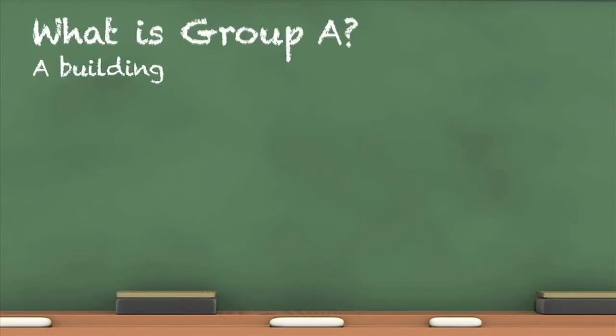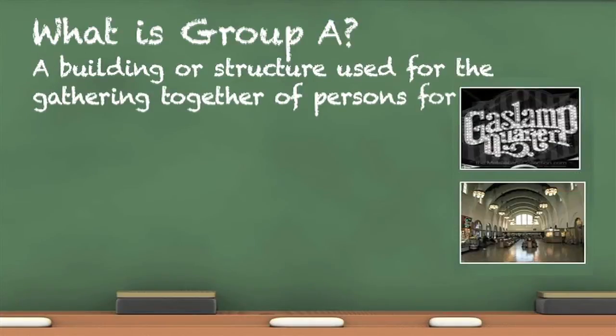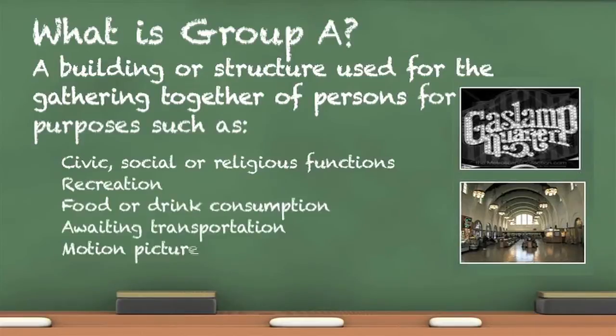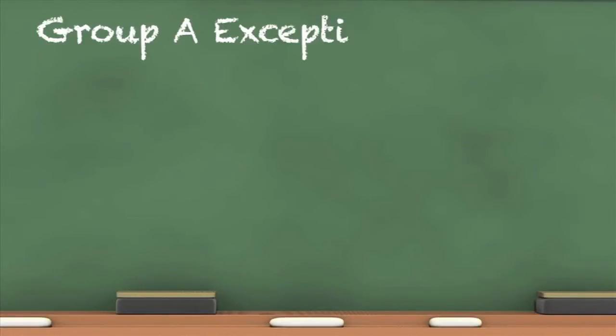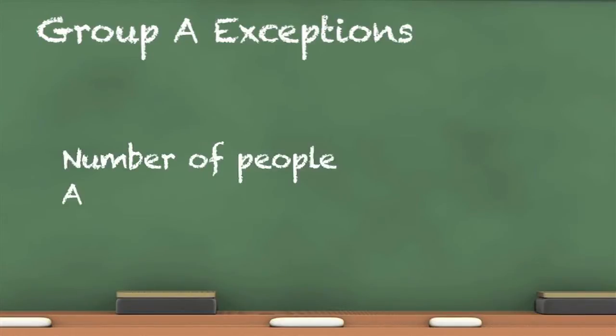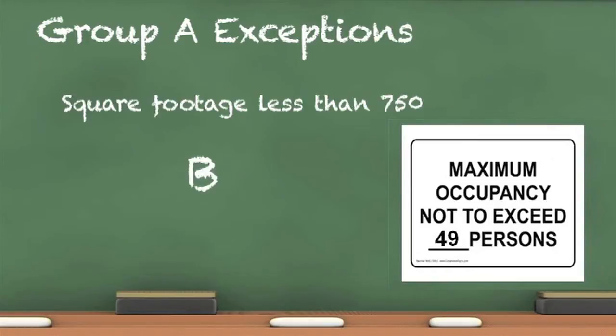Group A occupancies are defined as the use of a building or structure for the gathering together of persons. The type of gathering dictates the sub-occupancy classification. The number of people permitted to occupy the space, the amount of available space, and how it's used dictates whether or not an occupancy is classified as Group A. If there are fewer than 50 people or less than 750 square feet, it's Group B.